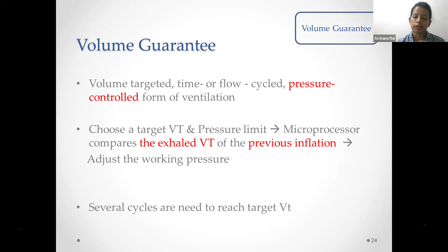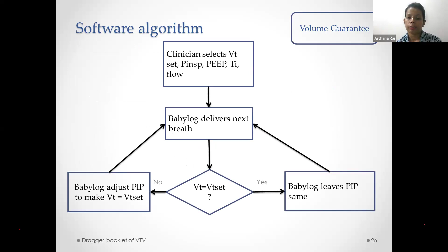VG can be combined with AC mode or SIMV or PSV modes. This is the algorithm. We set the tidal volume, we set the PIP limit, we set the PEEP, TI and the flow. Then the ventilator delivers the breath and it will see how much tidal volume is generated. In this figure, it will be much clearer. First we set a targeted tidal volume. This is the targeted tidal volume, and this is the pressure limit we have set for the baby.